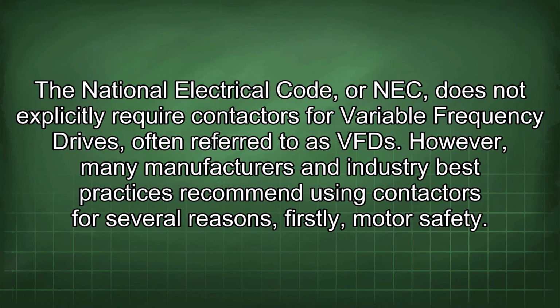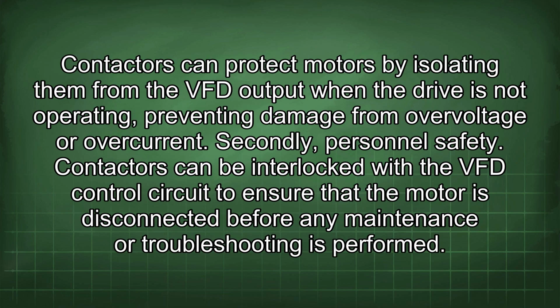The National Electrical Code, or NEC, does not explicitly require contactors for variable frequency drives, often referred to as VFD. However, many manufacturers and industry best practices recommend using contactors for several reasons. Firstly, motor safety. Contactors can protect motors by isolating them from the VFD output when the drive is not operating, preventing damage from overvoltage or overcurrent. Secondly, personnel safety. Contactors can be interlocked with the VFD control circuit to ensure that the motor is disconnected before any maintenance or troubleshooting is performed.